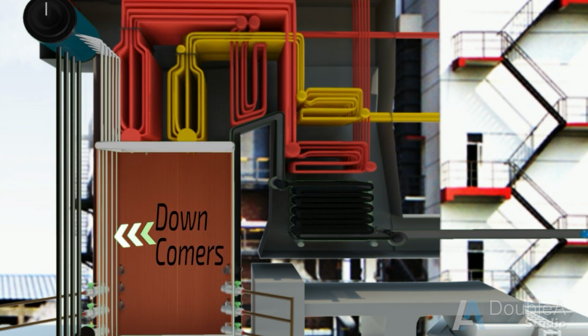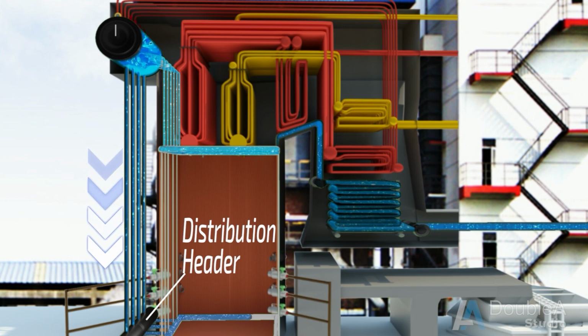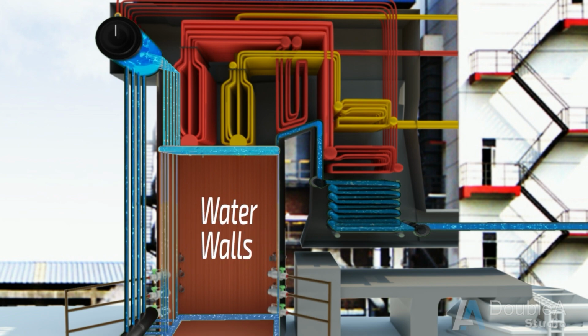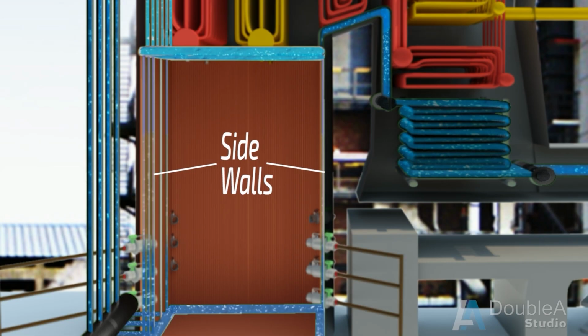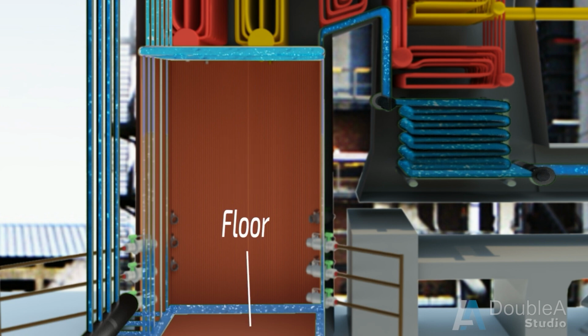Now we come to downcomers and risers or water wall tubes. Downcomers are tubes that supply water from the boiler drum to distribution headers at the lowest part of the furnace walls. Water walls or risers are a series of tubes welded together to form the walls of the combustion chamber. It typically has 2 side walls, rear wall, front wall, floor, and the roof section.